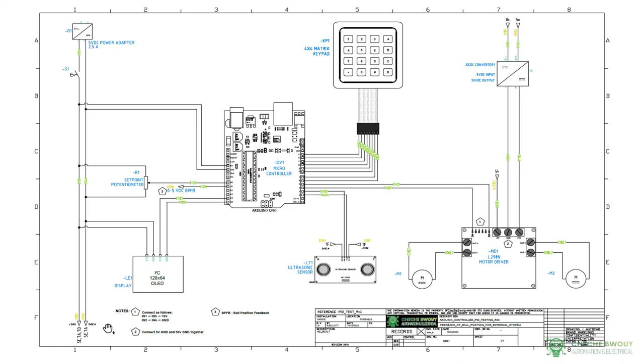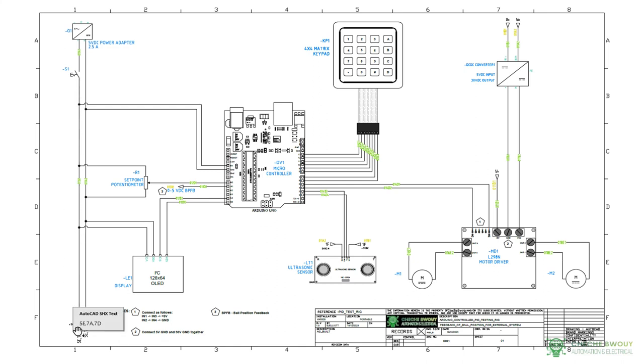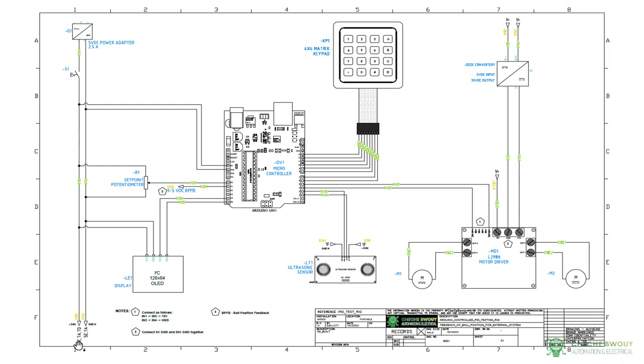Another thing to note is source and destination arrows. So right here you see this is a source arrow, which means this wire that's going through is continued at these destinations here in these grids: 5E, 7A, 7D.